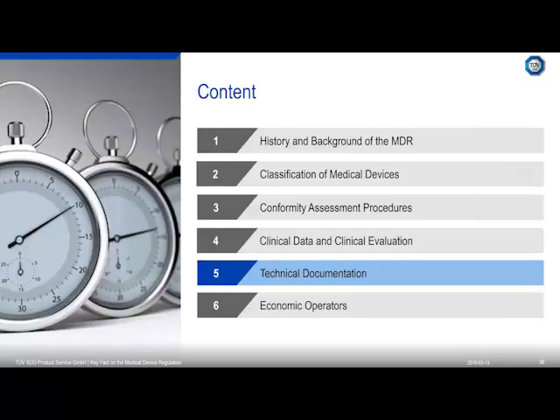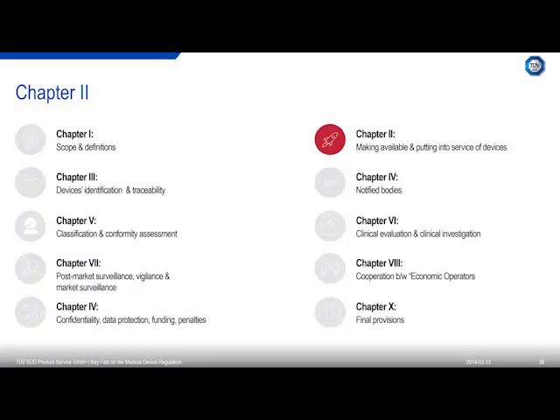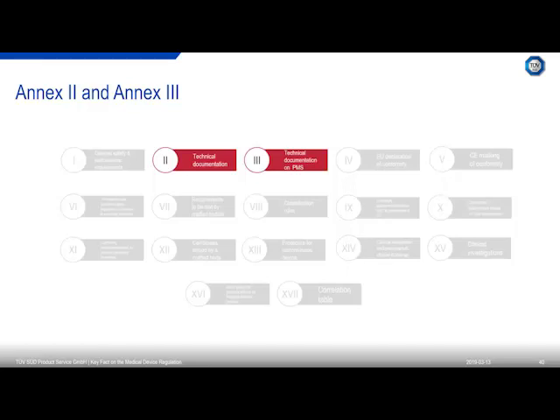And that brings us now to the technical documentation, because the clinical information is also part of the technical documentation, but there is a lot of other stuff that needs to be in your technical documentation. Your technical documentation is defined under Chapter 2. So the requirement of having one comes from Chapter 2 of the Medical Device Regulation and is now highlighted in Annex II and Annex III, and that is something that is better than under the current legislation, because today we don't have a proper definition of what a technical documentation is and what needs to go into it. So by this, we now have a proper definition by following Annex II and Annex III.